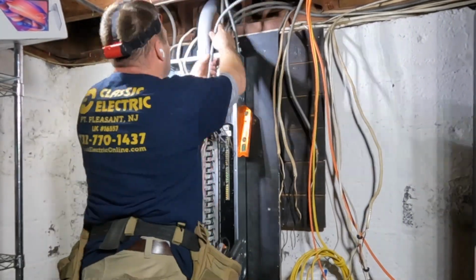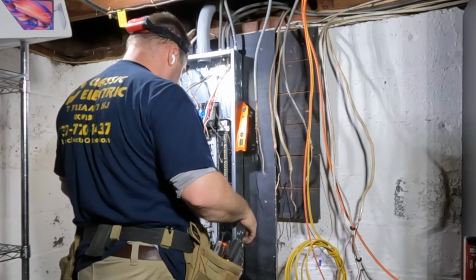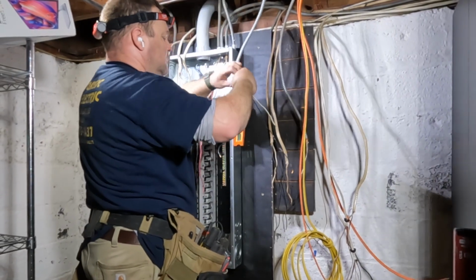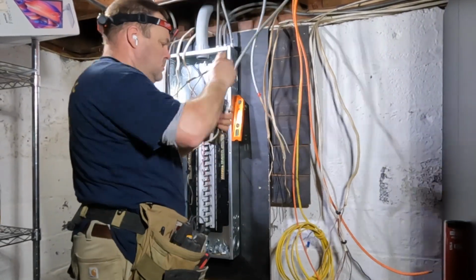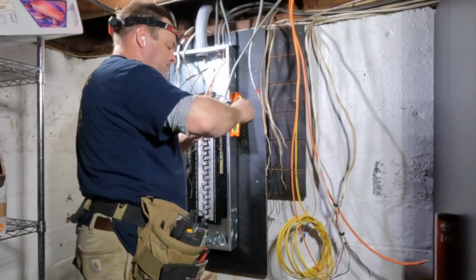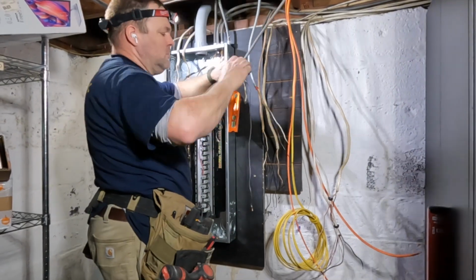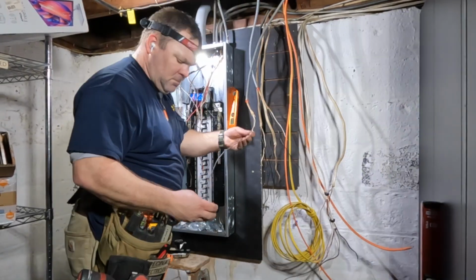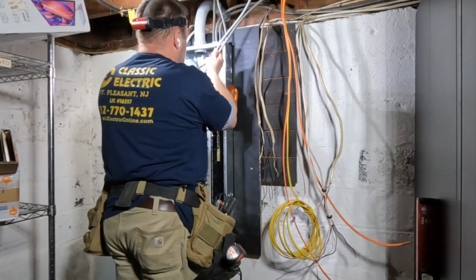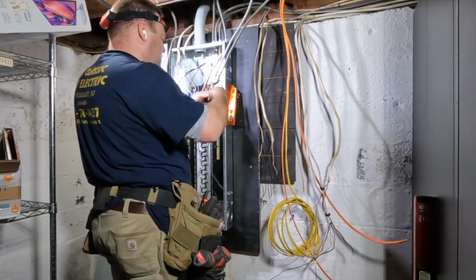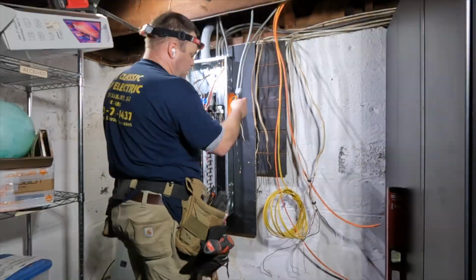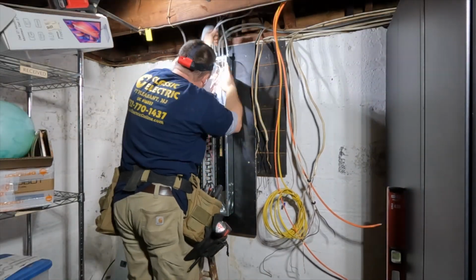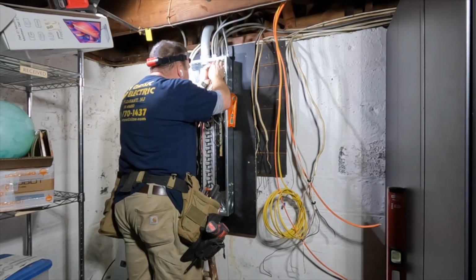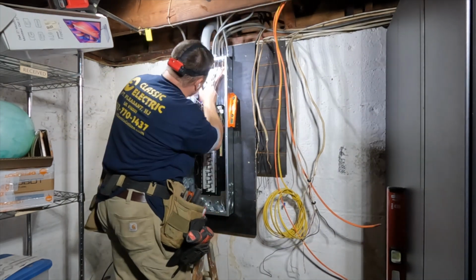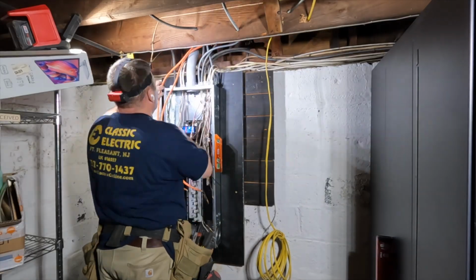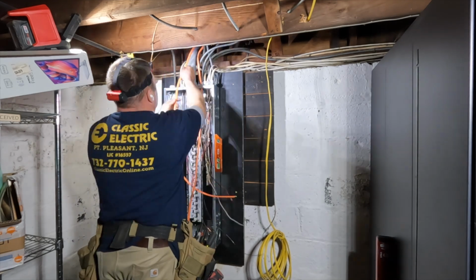For a few hours here in the basement, I'll be trimming back the home runs coming into the panel and getting them onto connectors and into the enclosure. With armored cable, the connector must be tight around the cable, and the lock nut must be very secure around the enclosure so we get a proper bond, because the outer sheathing of the armored cable, BX cable, is the equipment grounding conductor.